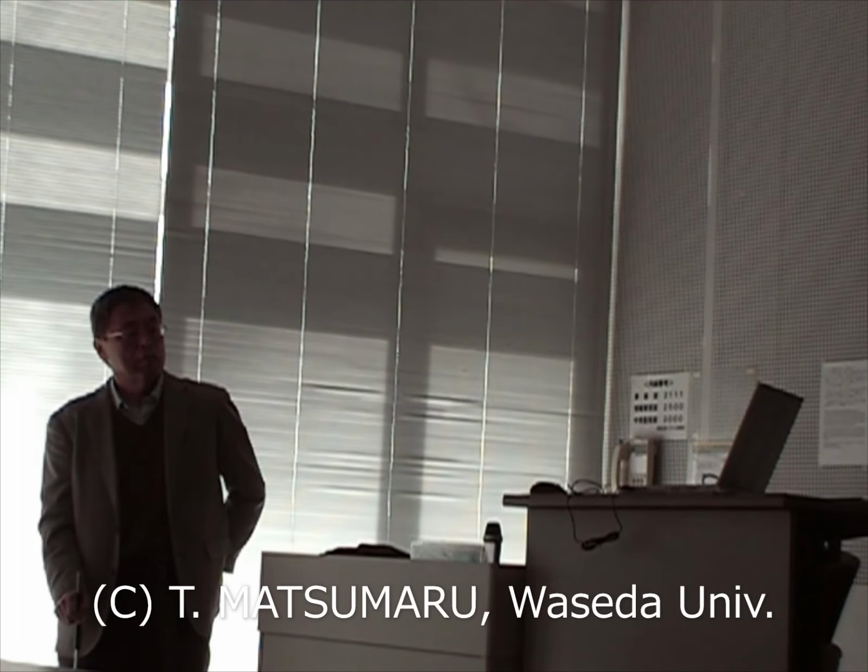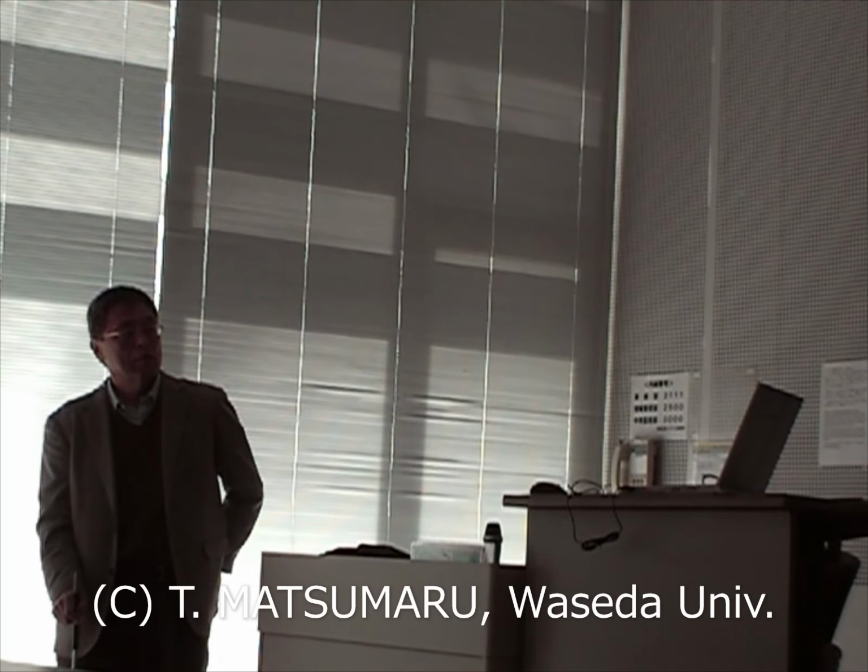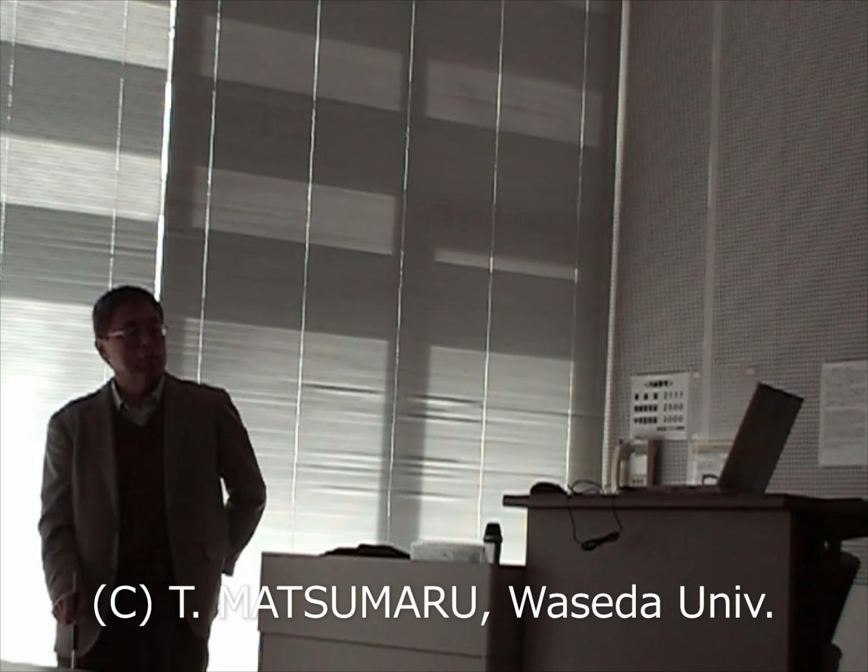We apply the pads, and there are 4 pads that are placed on every single patient. We have 2 pads that are placed on the upper torso. It goes from the spinal column in the back and wraps around the front. Then we also have 2 pads that are applied on the patient's thighs. If the individual has a rather large abdomen, we want to try to cover as much skin as possible to cool as rapidly as possible. So we do have a universal pad that we can use as well on somebody with a rather large abdomen.